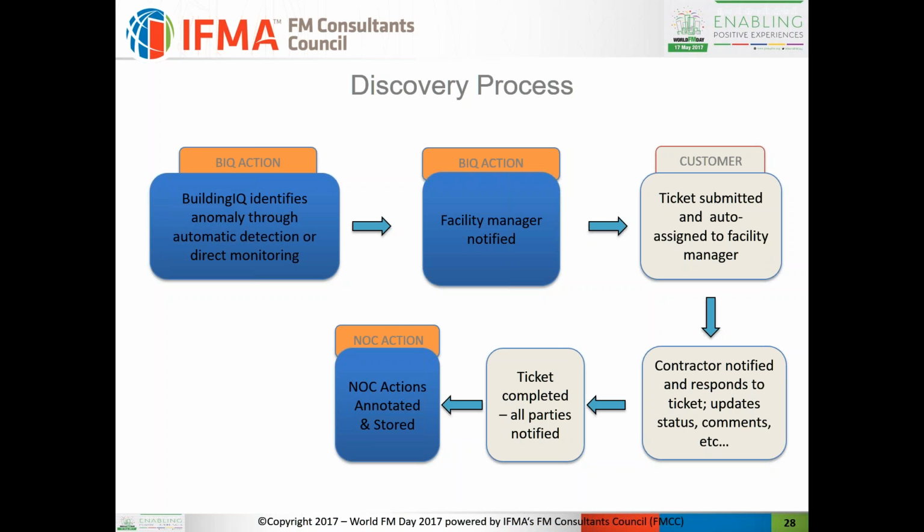While it's certainly a data check, it's also a manual gut check that says, hey, this stuff was done, and it looks like it had the right impact. It's annotated in the system and kept for the facility management team to access at any time, when they can go back in history directly and say, hey, this particular sensor, this particular unit had some issues. Let's see what it was in the past, and you can see that a sensor on that particular piece of equipment had failed. It was replaced, and it came back into expected action. We can see that in the traces, and we also annotate it and store it for posterity in the portal. So the facility team has a nice historical record of what's been going on from the data analytics side.